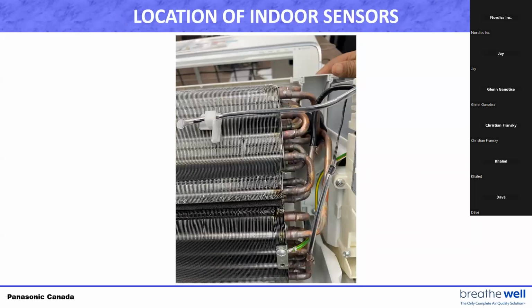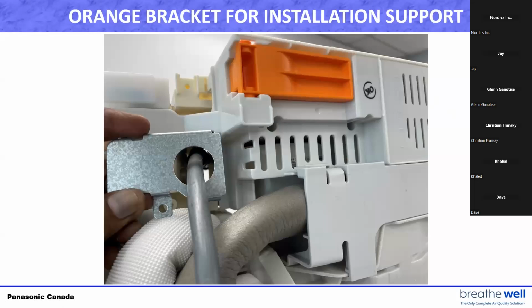The coil sensor, the top sensor there is your pipe in, and the bottom there is pipe out. Pipe out was somewhere in the middle. Now they have moved it to the very bottom. The ambient sensor is the same, in the same location. So we are hoping for something good and something better to take place come this winter, when all these units are out and about. As you can see, that orange piece there is to rest the unit on the wall, so that you can do your pipe connection, wiring connection, and insulation of the pipe connections after you're done with the flaring and stuff like that.